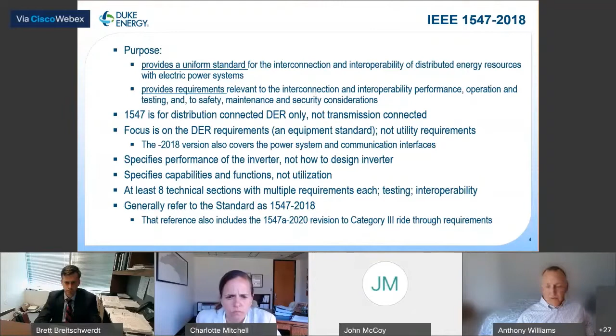So as we talked about, it's about performance of the inverter, not how to design it, or about the functions, not the utilization. And there's at least 8 main technical sections with many requirements in each section. And then towards the end of 1547, there's 2 other large sections for testing and interoperability. And a little bit of a finer point, but we tend to still call the standard 1547-2018, although there is a small revision in 2020 for category 3 ride-through, but we still just generally say 1547-2018.